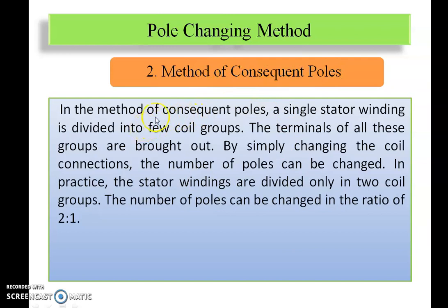In the method of consequent poles, a single stator winding is divided into few coil groups. The terminals of all these groups are brought out. By simply changing the coil connections, the number of poles can be changed. In practice, the stator windings are divided into two coil groups, and the number of poles can be changed in the ratio of two to one.